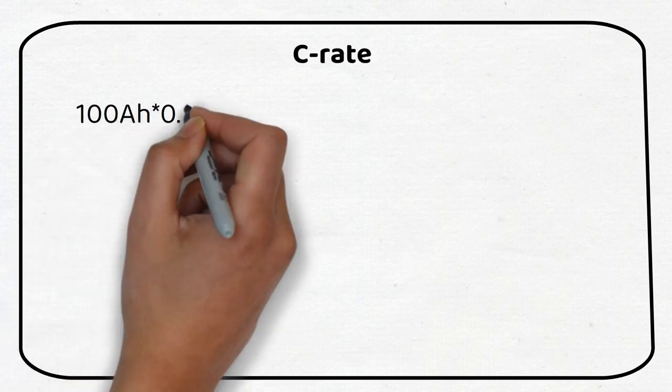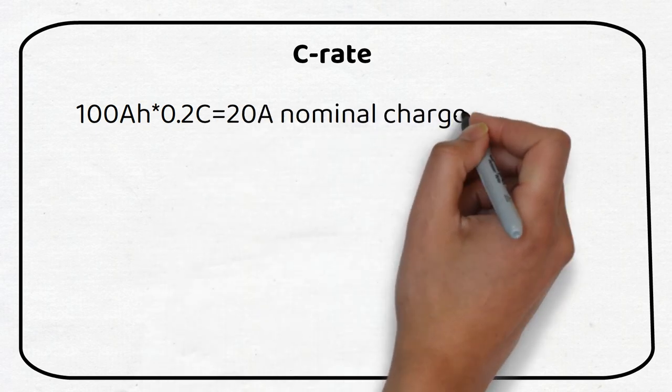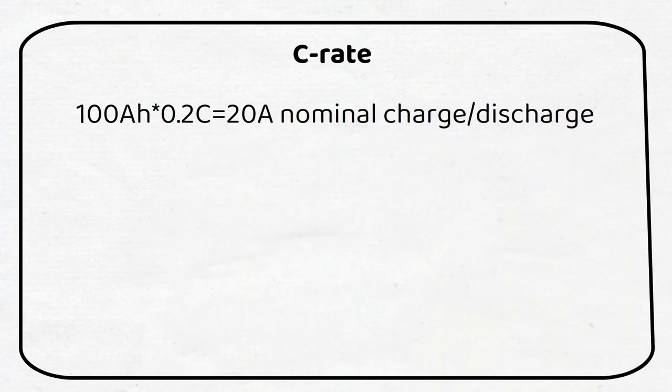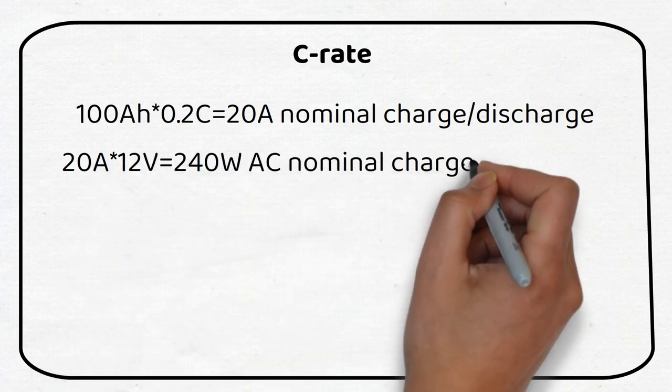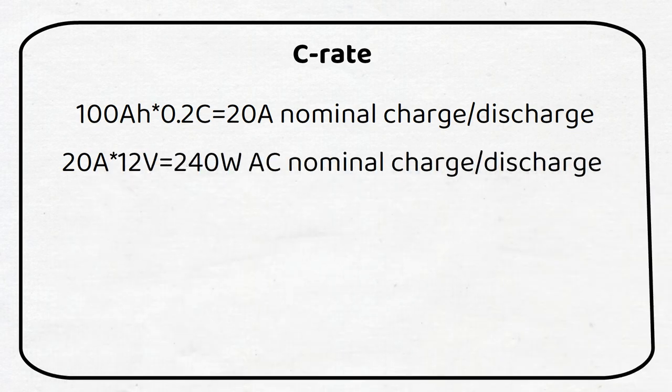What about the C rate? The normal C rate of lead acid battery is 0.2 C. This means that our 100 amp hour battery can deliver a nominal charge and discharge current of 20 amps. If we calculate this it's only 240 watts.